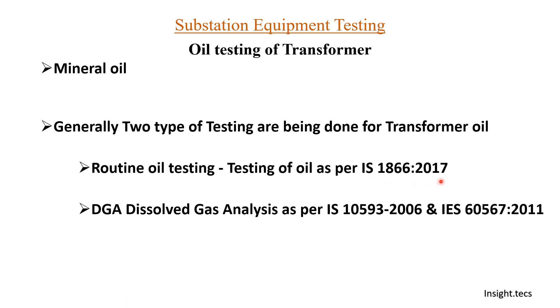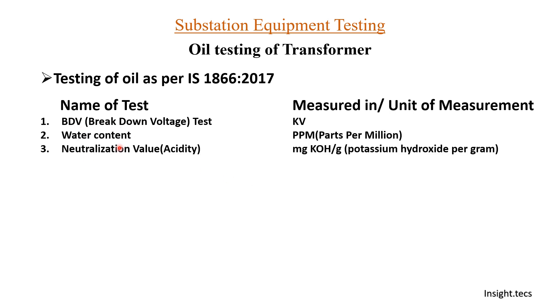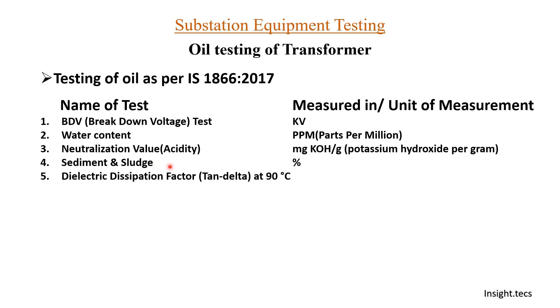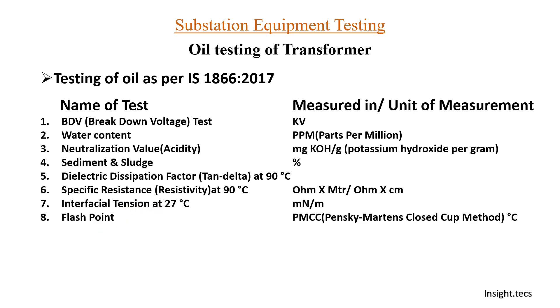Routine testing is done based on the standard IS 1866:2017. We have already covered four routine tests: first is breakdown voltage test, then water content, neutralization value or acidity, and sediment or sludge. Now in today's video we will see dielectric dissipation factor that is tan delta, specific resistance or resistivity at 90 degrees, interfacial tension, and flashpoint.